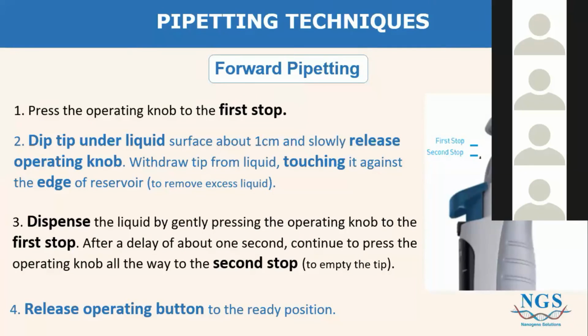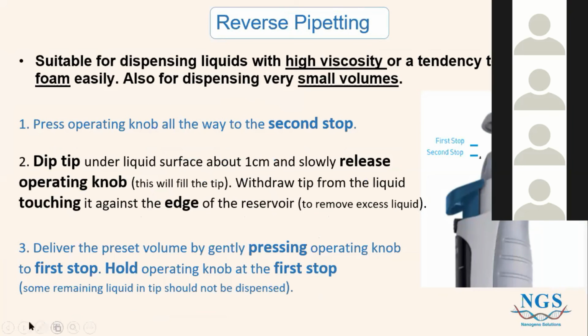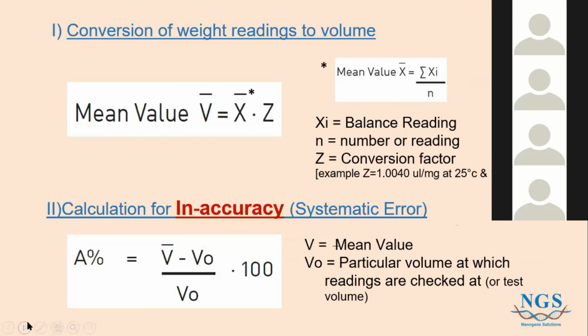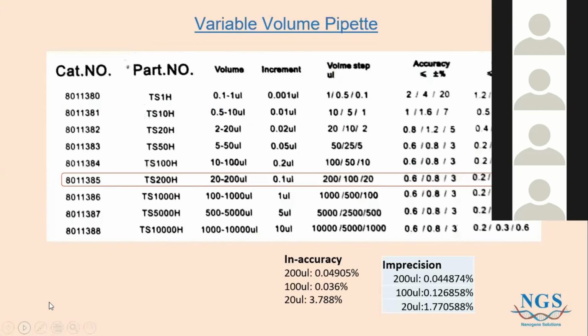Okay. Is the procedure to verify pipette accuracy the same as your procedure to check calibration? Yes. So as I said, hold on, let me get into that slide. Yes, Hanli. So your question is whether the calculation for inaccuracy is kind of like validating if your pipette needs to be calibrated? Yes, you're correct. So when you're calculating inaccuracy, you want to be very mindful. If anything is out of the range of inaccuracy, it means that your pipette needs to be calibrated. So that is what inaccuracy can tell you. That would be the systematic error. It is kind of like an error that you can predict, something that tells you your pipette is probably not in a very good condition.